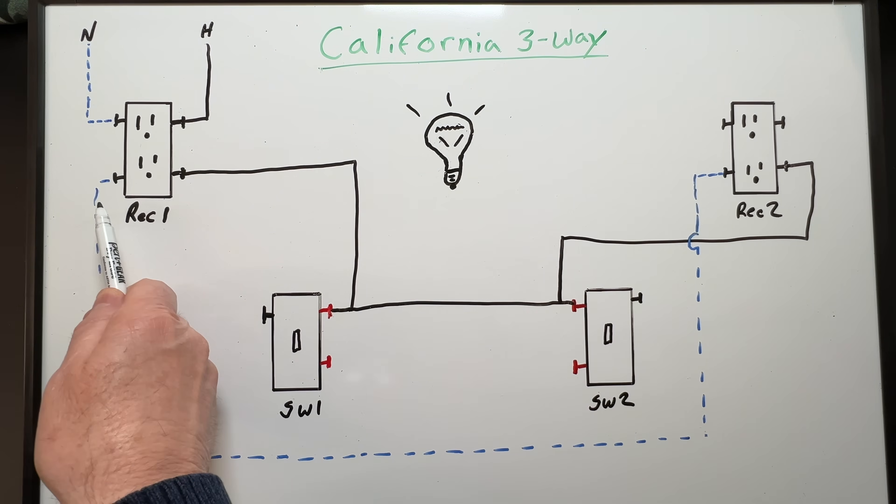Our white neutral wire from receptacle one will bypass our switches altogether and go directly to receptacle two. We now have a complete circuit path from receptacle one all the way over to receptacle two. Our line power comes from receptacle one goes down to switch one across to switch two and up to the receptacle. Then our neutral return returns current back to the source. So receptacle two will now have power regardless of the position of our three-way switches. And our receptacle circuit can continue on to other lights and receptacles as well.